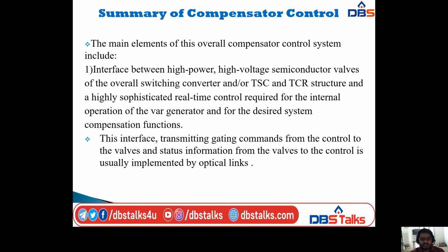That's why I mentioned this is the first main element: the interface between the high power, high voltage semiconductor valves of the overall switching converter, that is the TSC and TCR structure, and a highly sophisticated real-time control required for the internal operation of the SVG and for the desired system compensation function. This interface transmits gating commands from the control to the valves, and status information from the valves to the control, usually implemented by optical links.